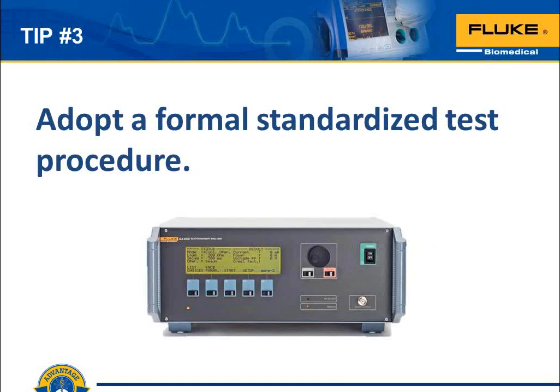Tip number 3, adopt a formal standardized test procedure. So once again, we all prefer the inspection procedure from the medical device manufacturer, the model-specific one found in the service manual. But sometimes that's not available. It's still the responsibility of the biomed department to come up with a standardized test procedure, something you use all the time, year after year, inspection after inspection.